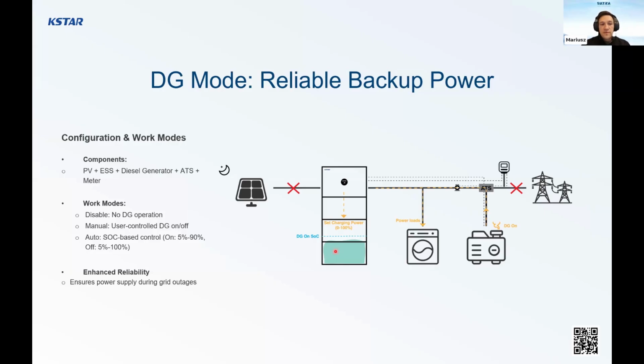So we can work with this diesel generator, and in the diesel generator mode, we define two SOC levels: the DG SOC level on and the DG SOC level off. Of course, both of these conditions work only at off-grid time. So in case we have a power outage and we are using our batteries, and we started from 80% of the SOC and go down to 30%, then we decide to turn on the DG, and if we reach 50%, for example, we turn off the DG.